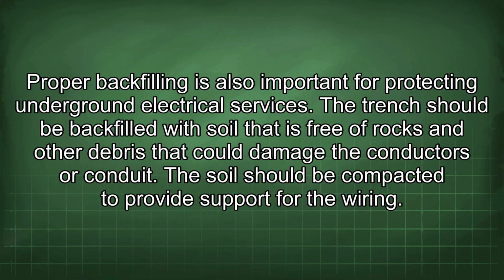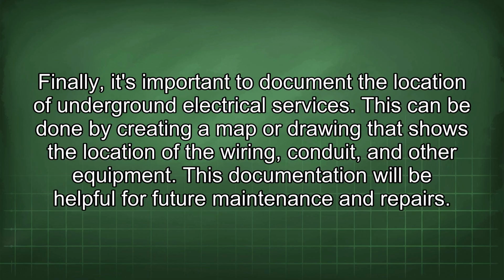Proper backfilling is also important for protecting underground electrical services. The trench should be backfilled with soil that is free of rocks and other debris that could damage the conductors or conduit. The soil should be compacted to provide support for the wiring. Finally, it's important to document the location of underground electrical services. This can be done by creating a map or drawing that shows the location of the wiring, conduit, and other equipment. This documentation will be helpful for future maintenance and repairs.